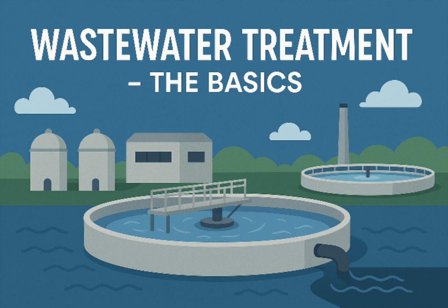After screening, the water flows into what are called grit chambers. These are designed to slow the flow down just enough so heavier inorganic stuff settles out. Things like sand, cinders, eggshells. Especially important if you have combined sewers, I guess, where rainwater mixes in. Exactly. That stormwater washes a lot of grit into the system. You want to get that out early so it doesn't damage pumps and equipment down the line. Makes sense. Abrasive stuff. Then sedimentation tanks or clarifiers.